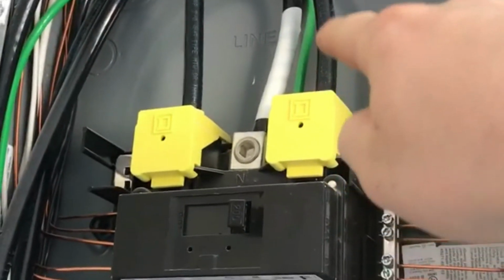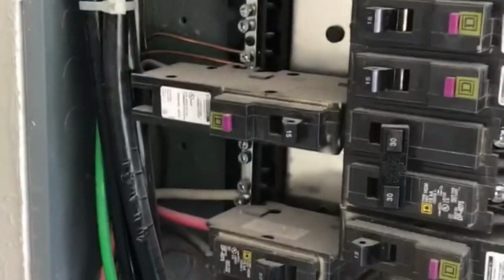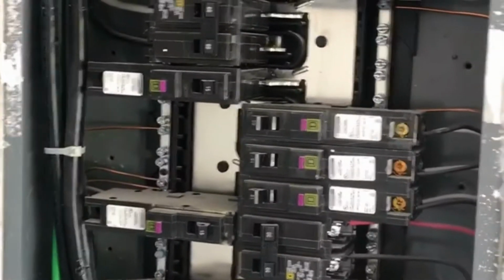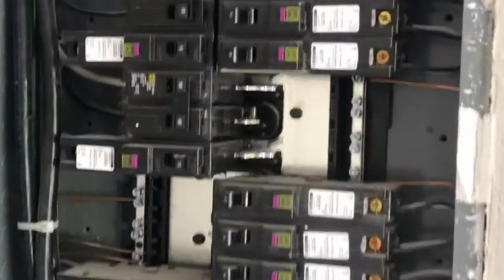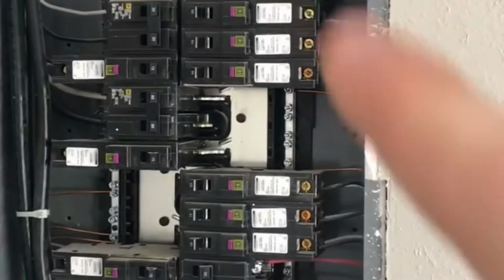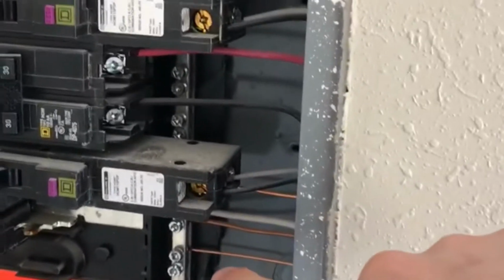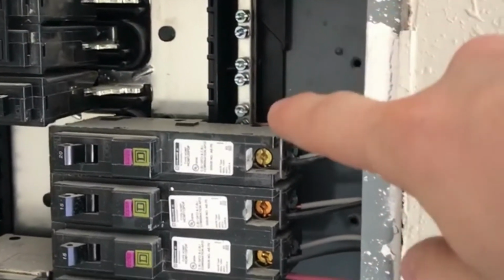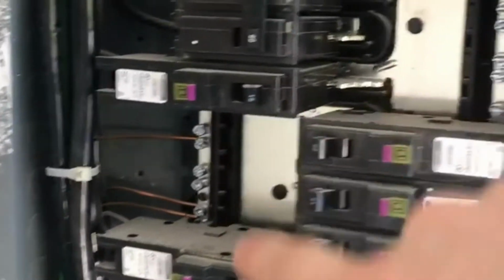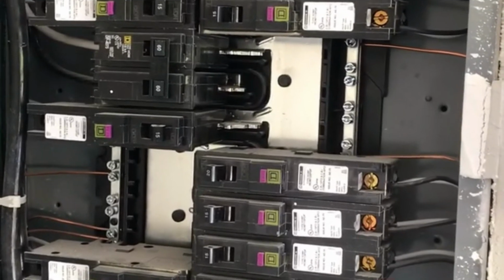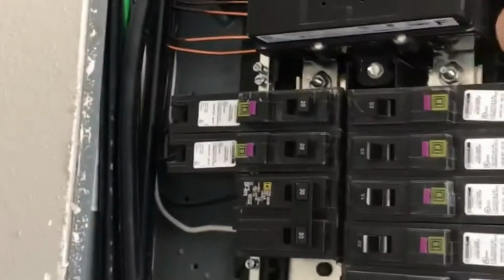At the top here is our green ground wire that goes back out of the house, where it will be attached to a ground rod, which is driven into the ground, grounding any electrical components out of this breaker box. On the sides, the silver bars are our ground and neutral bus bars, where we attach any ground and neutrals to complete the circuit, while also grounding them to the green wire.